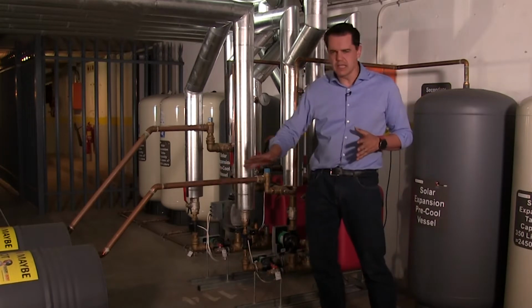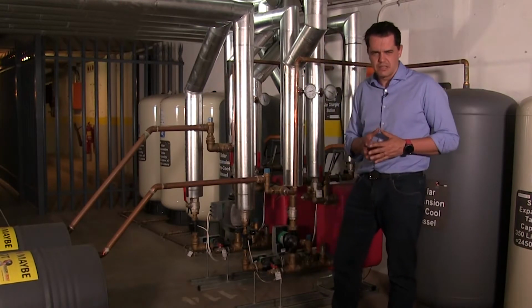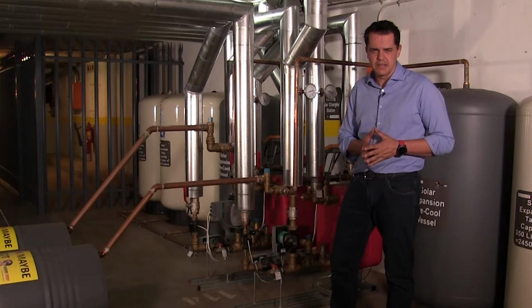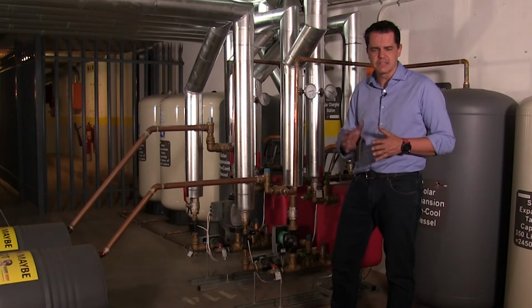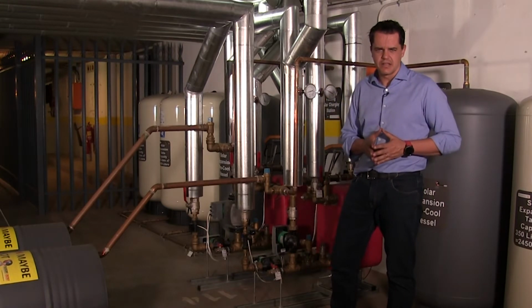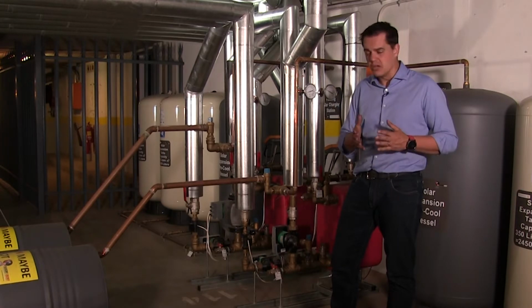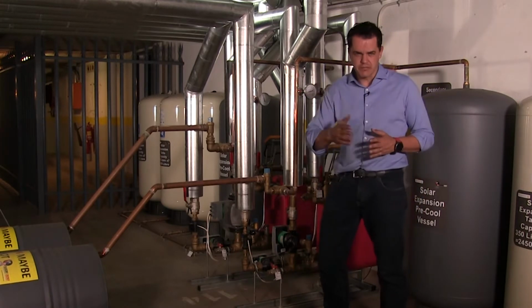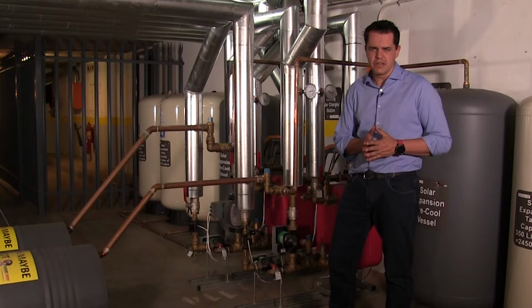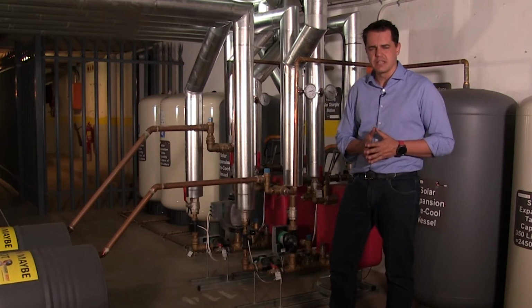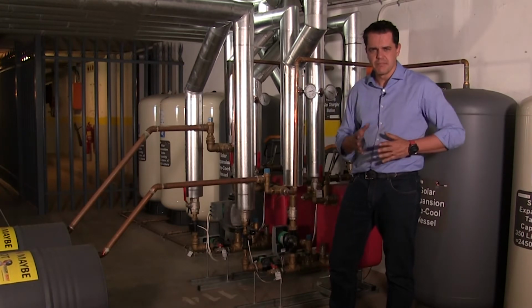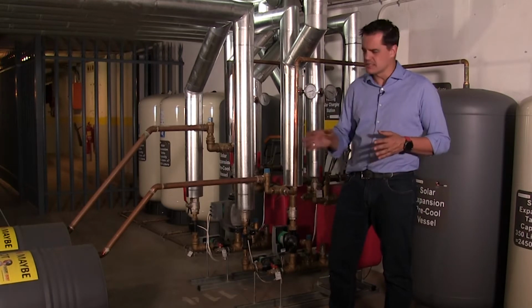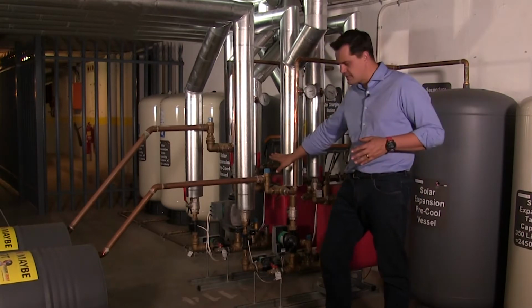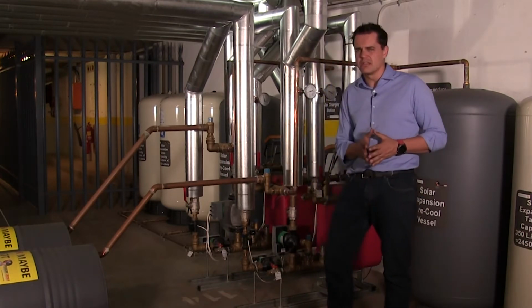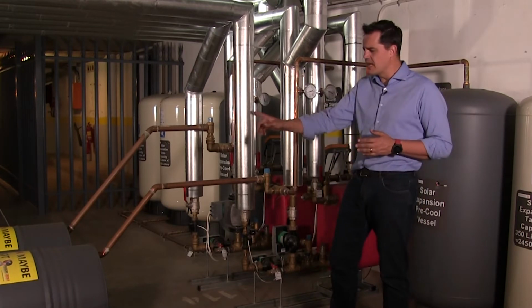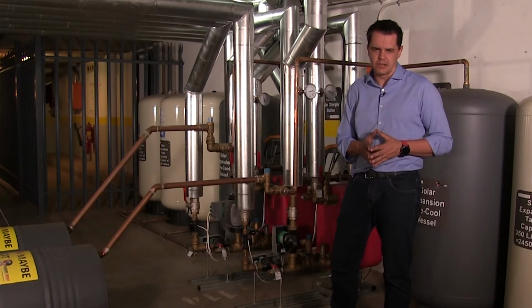And by merely looking into the drum, you can identify that the glycol has been expanded or released into the tanks, you can contact the contractor and notify them that the system has in fact gone into a safety pressure release. The glycol is released into the drums. The contractor needs to come back on site, replace the valve because it's only intended to really open once, and then reload the system with that glycol.